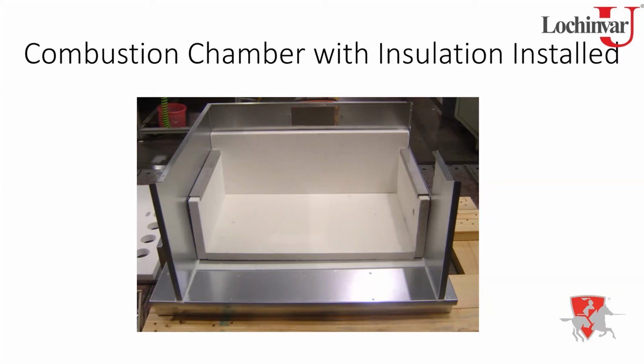One thing about the ceramic tile I'll mention is it does not like to get wet. It's a pretty durable material, but it doesn't like to have a lot of water standing on it for a long period of time. That water will eventually cause the binders in that material to start breaking down and it'll start dissolving. Typically on a startup, you get a little bit of condensation on an initial start. That's fine, that's going to dry up. It's where you maybe have a leak in the heat exchanger that is constantly wetting that fiberboard material that you run into a problem.